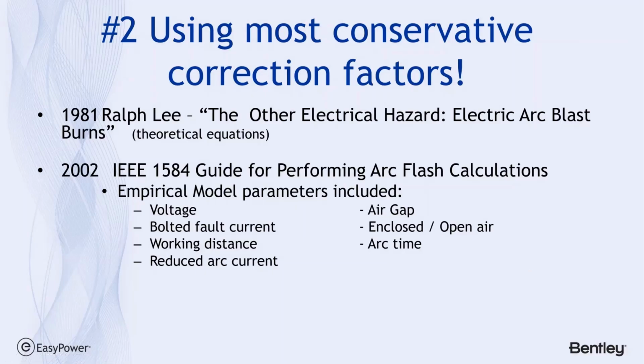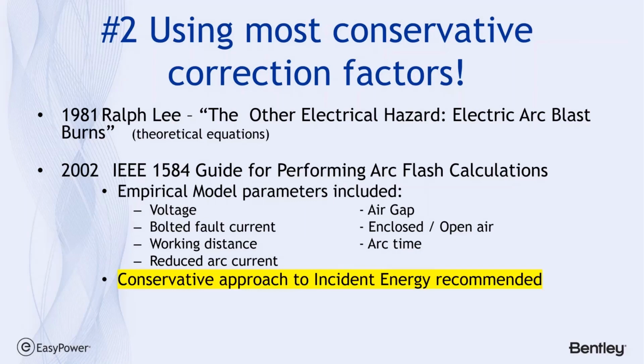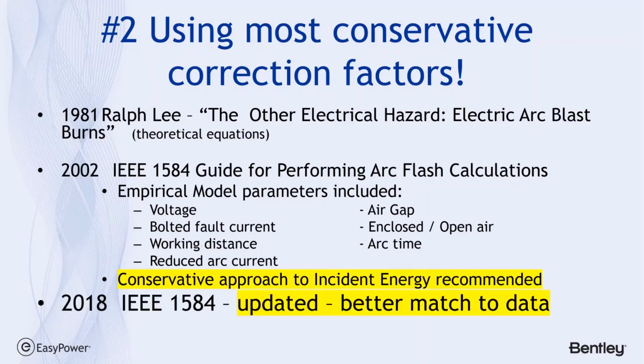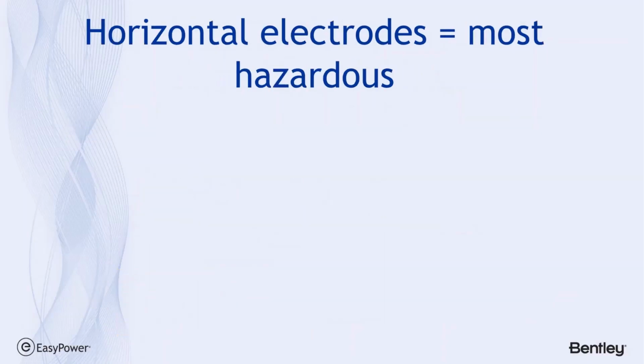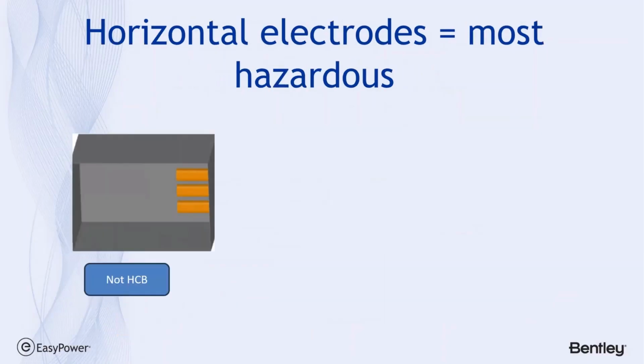Well, the problem is that originally in the 2002 release, we were encouraged to be conservative in our approach to incident energy calculations. But with the advent of the extra testing that was done in 2018, the updated model gave a better match to the test data. And so now we're being told that we don't have to be as conservative as we have been in the past. One of the examples of this is the classification and understanding the impact of electrode configuration.